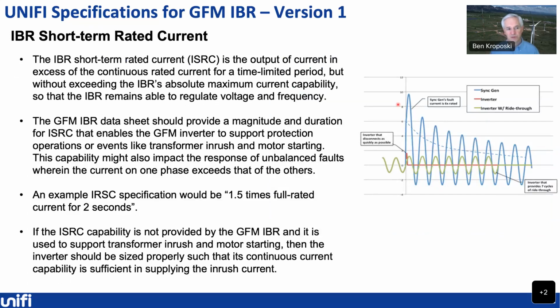And then things like short-term rated current. How much output current can you get from these inverter-based technologies is going to definitely be dependent on how they were designed. I'll just say that what we want to be able to do is specify what this short-term rated current is going to look like. Maybe it would be 1.5 times full rated current for 2 seconds. But inverters are going to have some amount of controllability in this aspect, and you may want them to have a lot of short circuit current or not a lot of fault current. And really that has to be designed into the system and discussed with how they're operated with the rest of the protection grid.